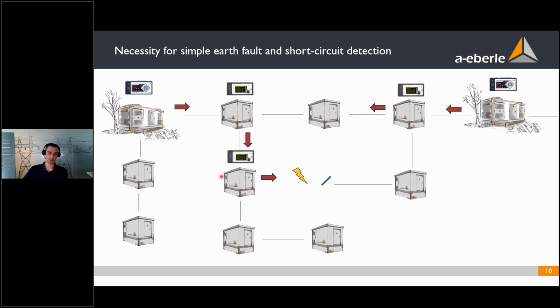That's why the installation of additional devices at important nodes of your grid is helpful for fault localization. And as you can see here, you have a few EOR-1DS installed inside of these simple stations, and then they all point into the fault direction. And that way, it's really easy to precisely locate the fault.